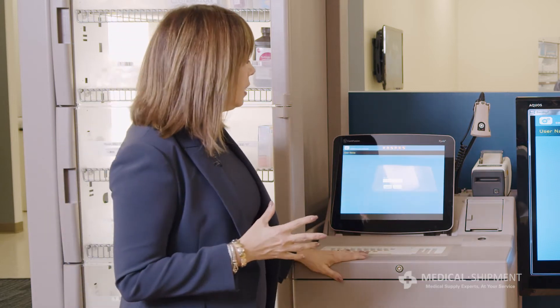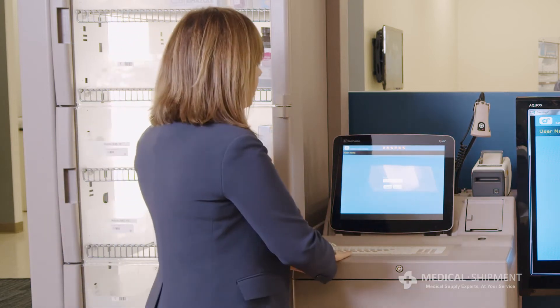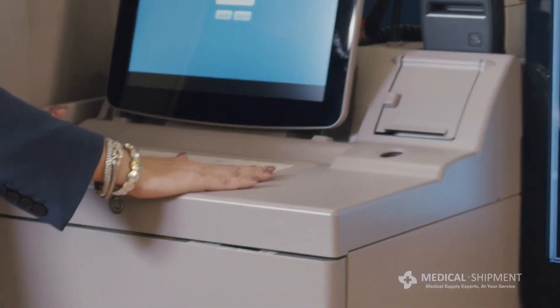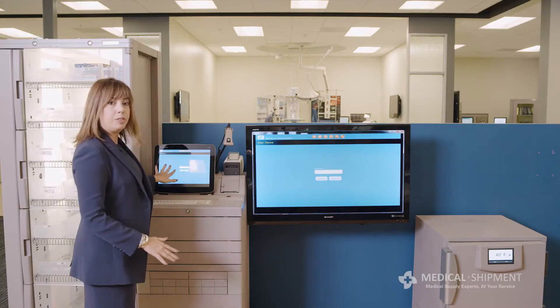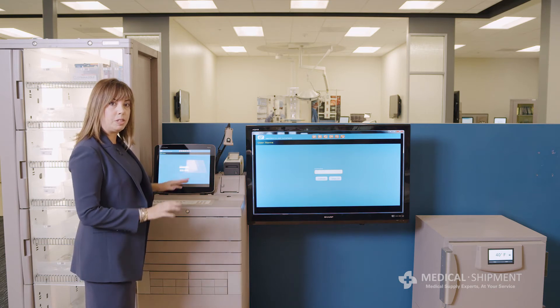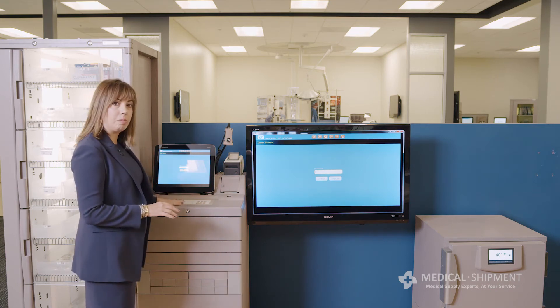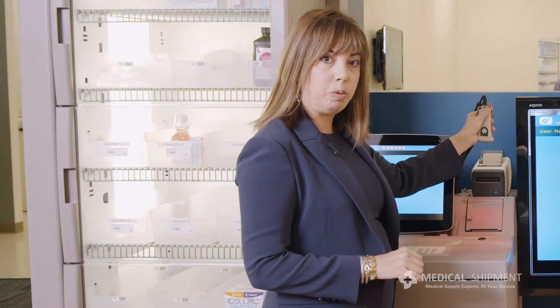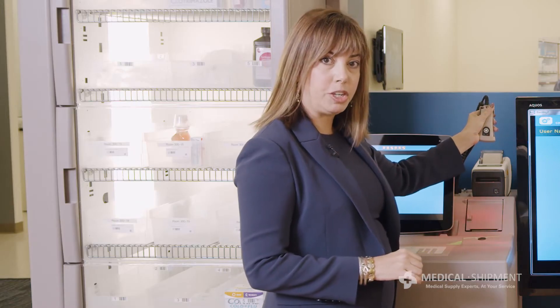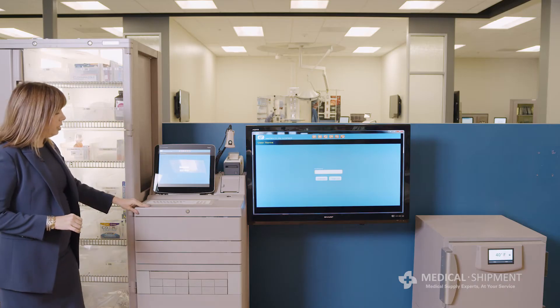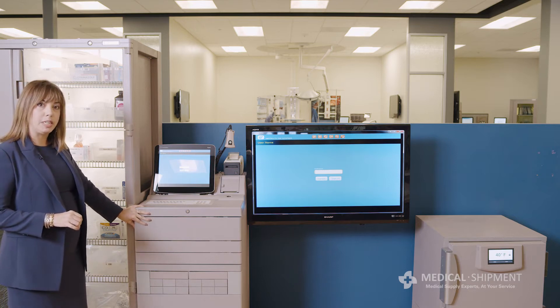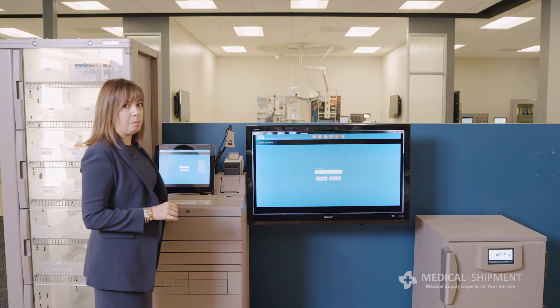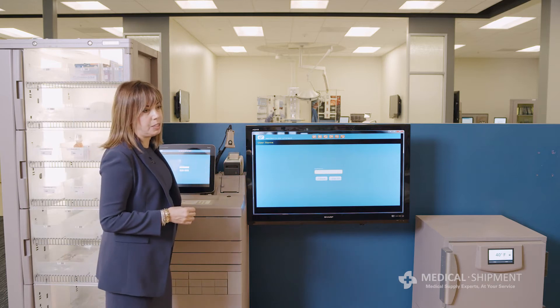This is the Pyxis system itself. There is a keyboard down here that can be cleaned easily and readily. There is a touch screen that allows us ease of use so we don't have to type, but we do have that opportunity when we need it. There is a barcode scanner to help with safe medication administration. Within the Pyxis unit itself are drawers that store the medication, and we'll take a look at some of the different ways that can be done as we progress through the discussion.